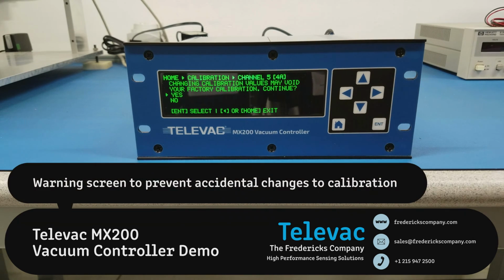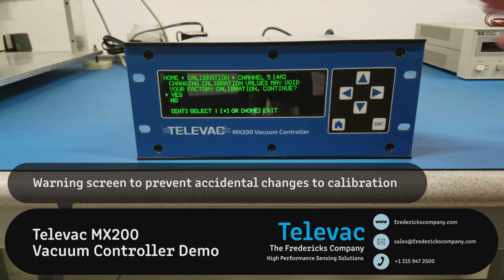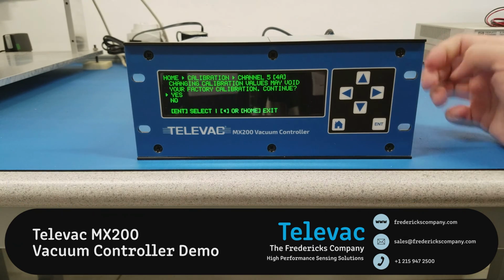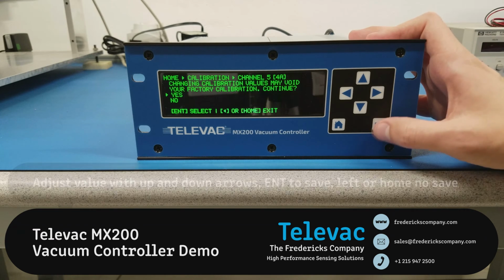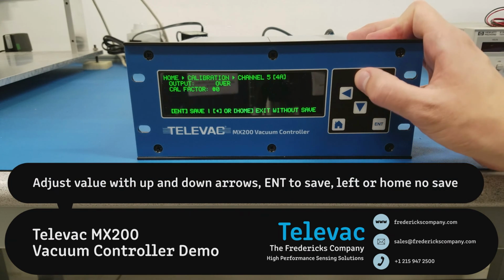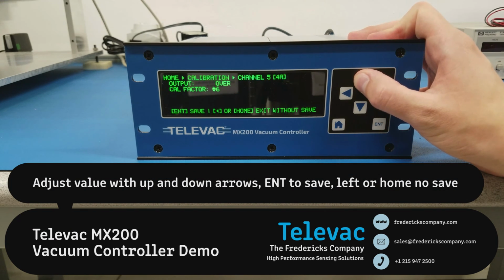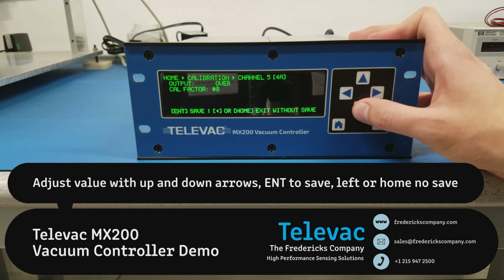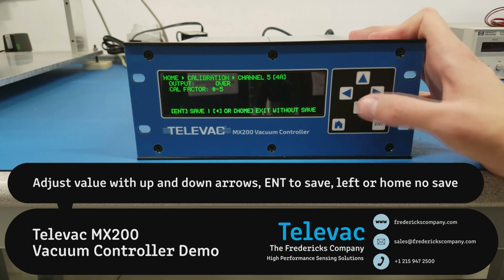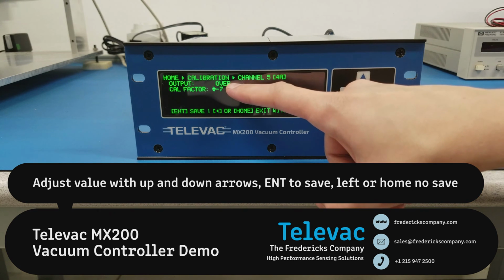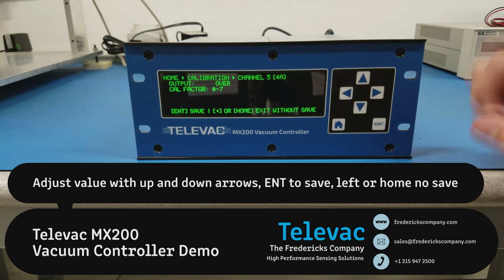So we put a warning in here to say, if you do this, you're going to void your factory calibration, whether it's NIST or standard. So you have to hit enter to continue. And you can adjust the calibration value up and down. And this value is going to range from -99 to 99. And the reading, as the calibration is changed, is displayed directly above it.